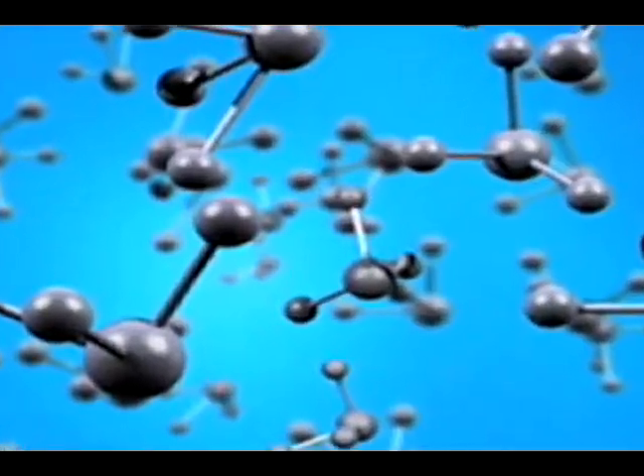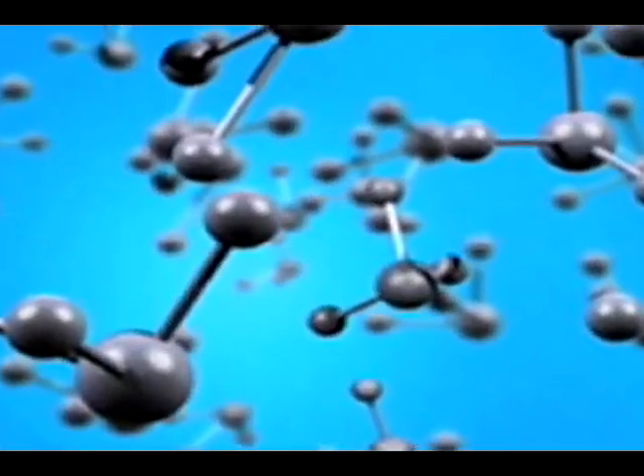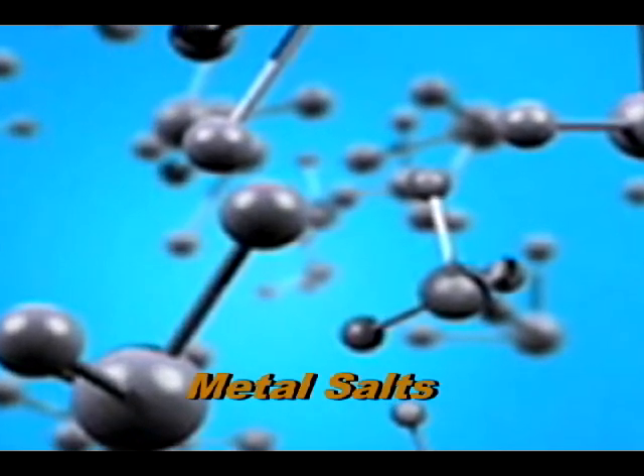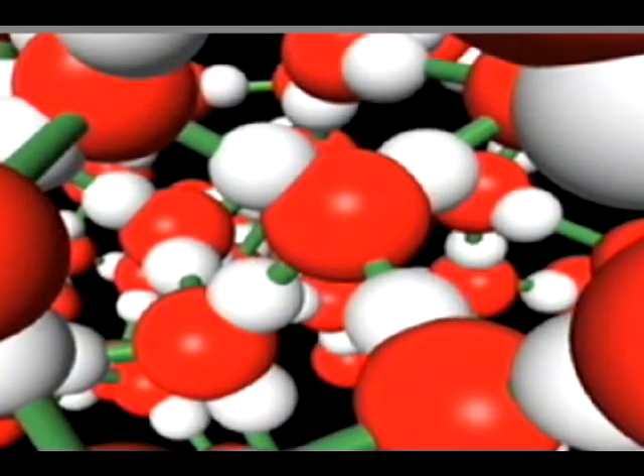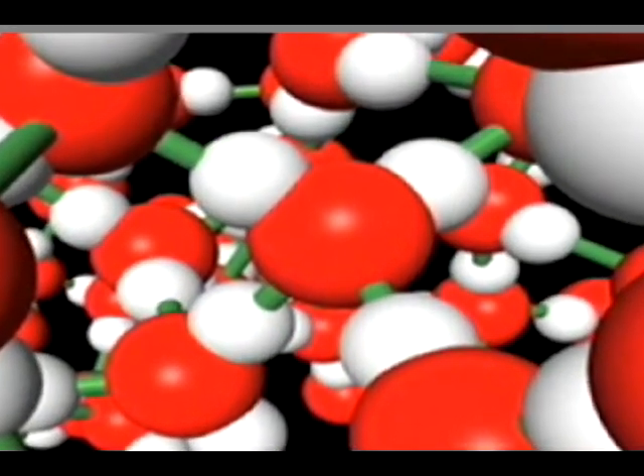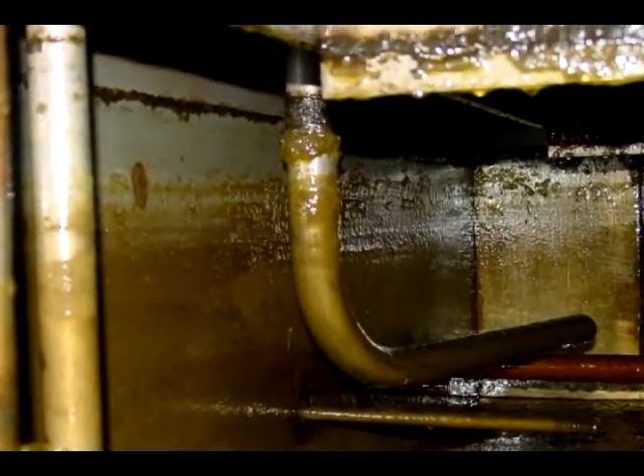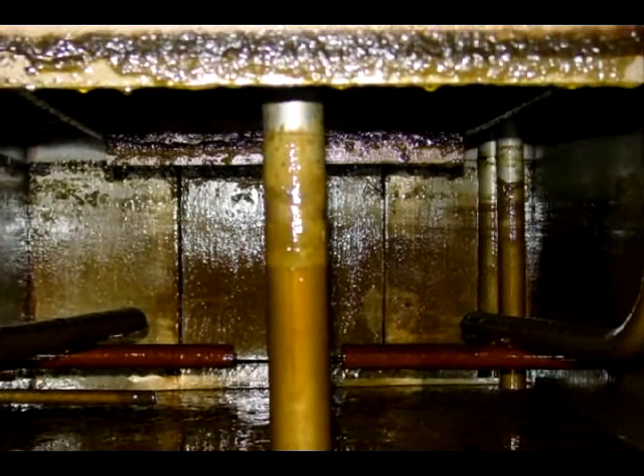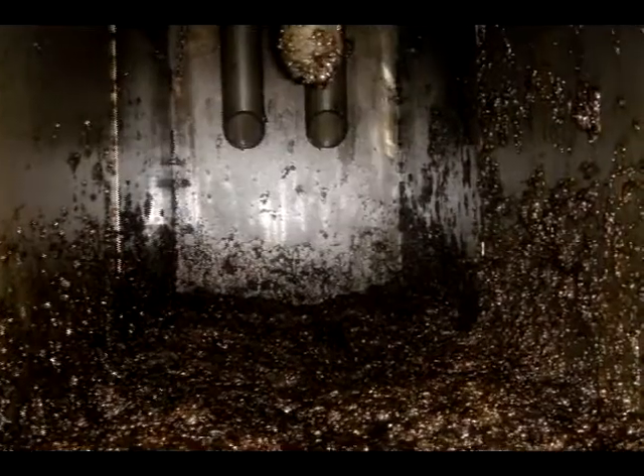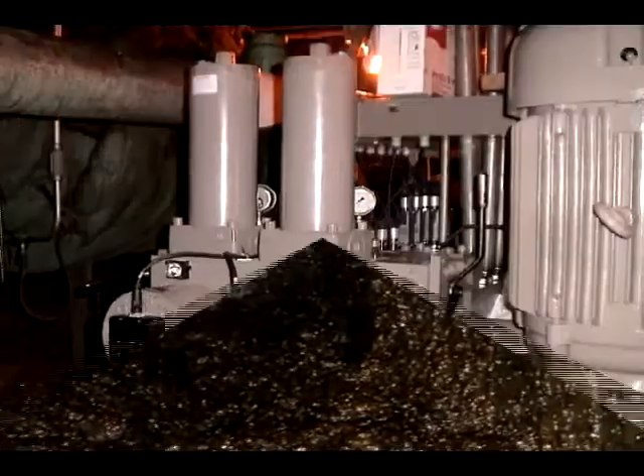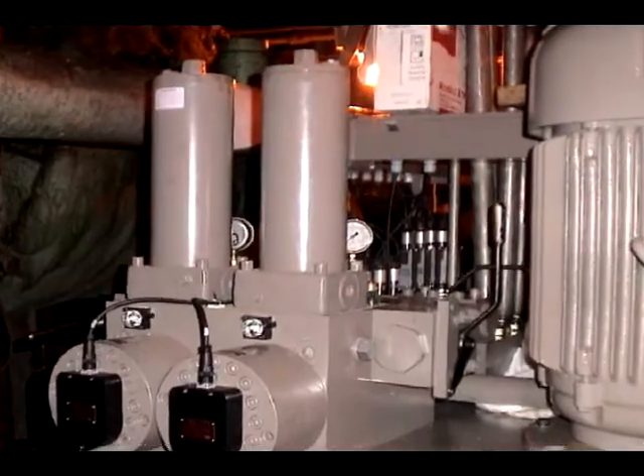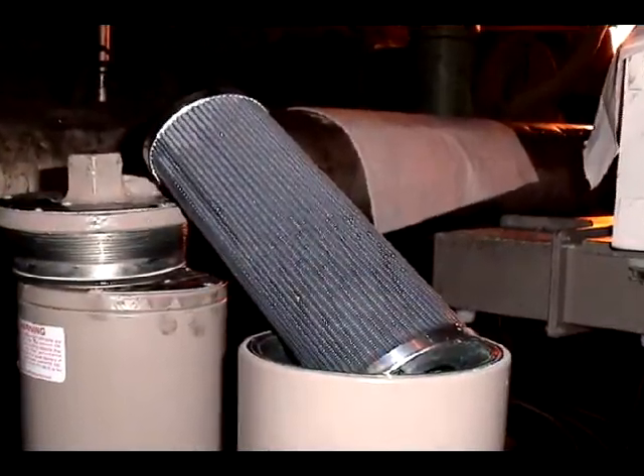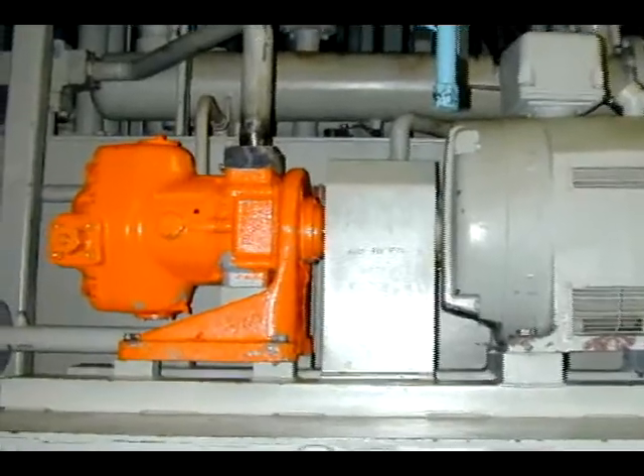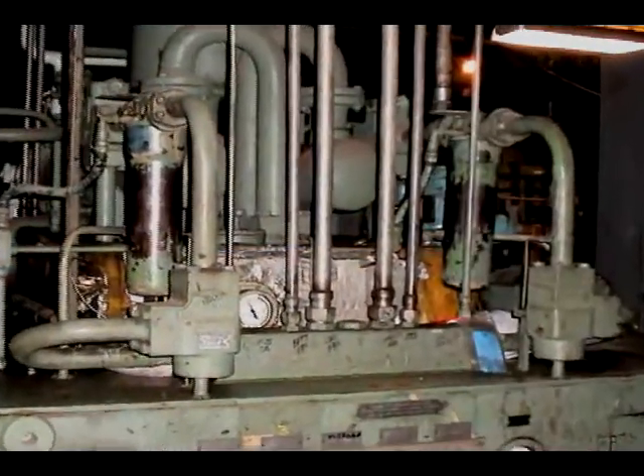During normal use, Fuller's earth filters continuously release small quantities of magnesium and calcium in the form of metal salts into the fluid. As the fluid's acid levels increase, these metal salts continue to be released in greater quantities. Metal salts in sufficient quantity ultimately cause a chemical reaction to occur in the fluid, which results in the formation of gels. Gels are simply FRF in a gel form with metal salts present. These gels are capable of passing through the smallest of filter media as long as there is sufficient flow through the filter. Once the gels are picked up by the hydraulic pumps, they are circulated throughout the entire hydraulic fluid system.